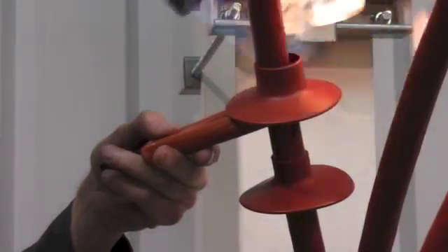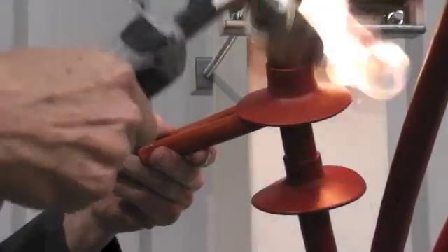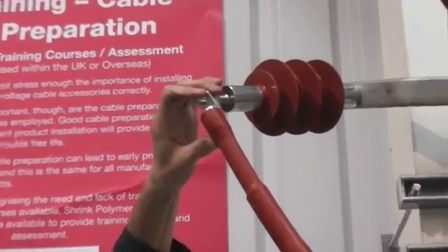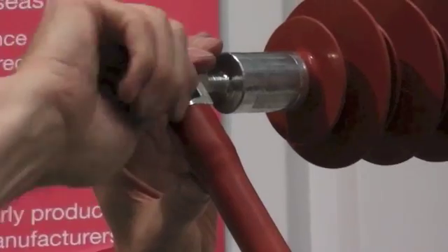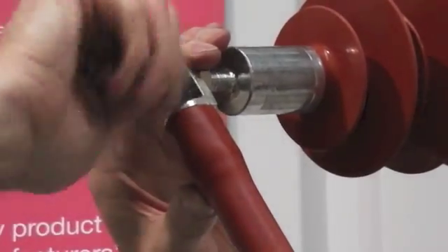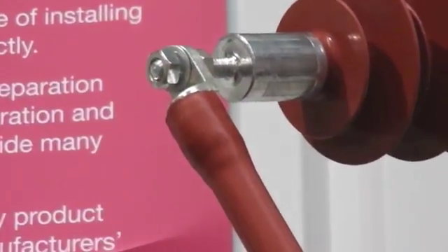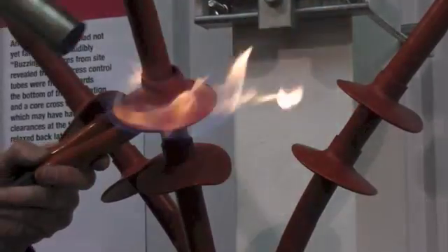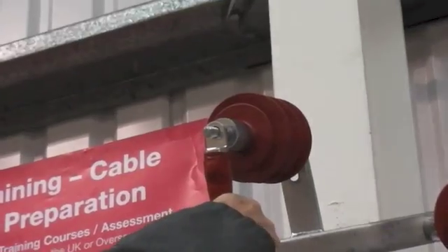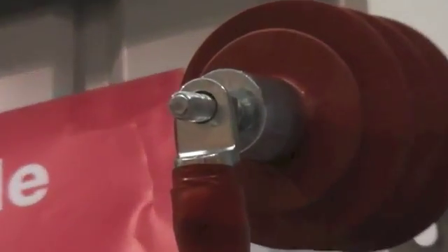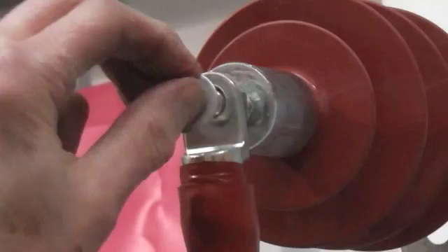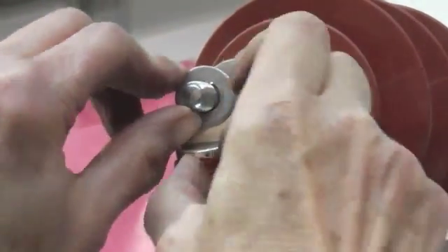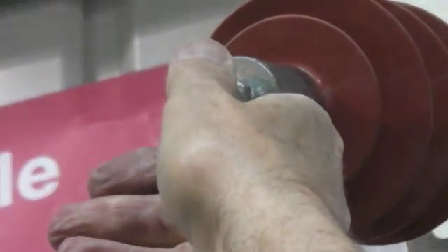Another problem area with outdoor terminations is the use of PVC tape to phase identify the cores. PVC tape will track and degrade. Moisture will get underneath, causing discharging, and eventual failure is likely. If you use PVC tape, remember to remove it once the cores are in their final destination.